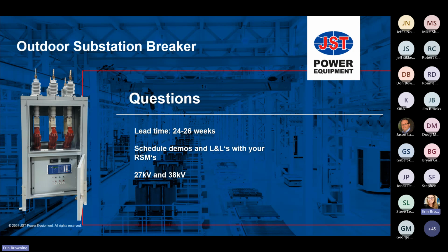The 38 kV breaker is a full-on redesign of the circuit breaker. Both projects are being looked at by R&D, are being actively worked on, and the plan is to take the 27 kV and the 38 kV to KEMA at the same time, and that's going to be overseas. I think it's in Amsterdam, actually. So that's the game plan. That KEMA test date is not on the calendar yet, but it's expected to be in early 2025. So we're thinking like mid 2025.